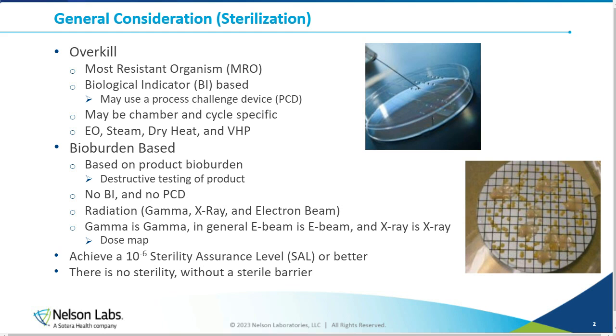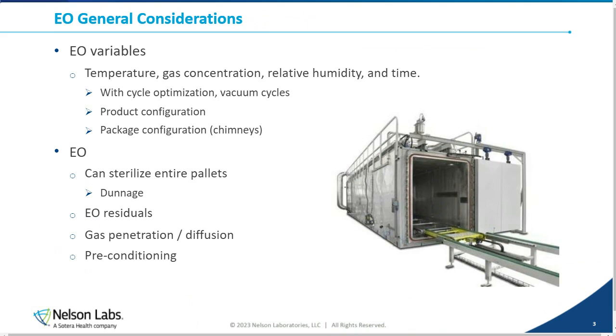With these methods, whenever we're talking about sterility and sterilization, what we're really talking about is our sterility assurance level. That's mostly going to be a 10 to the minus 6 sterility assurance level or better. The other thing to consider, and it's why I'm joined by my associates today, is that there is no sterility without a sterile barrier system. We can go through all the steps we want and sterilize it, but if there's not a sufficient sterile barrier system, then the second we pull it out of whatever's sterilizing it, it's no longer going to be sterile.